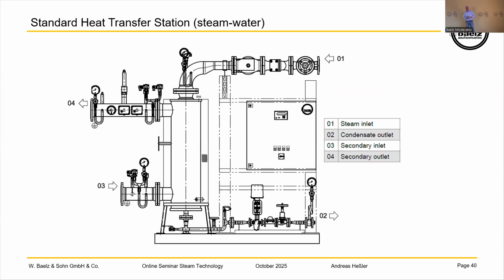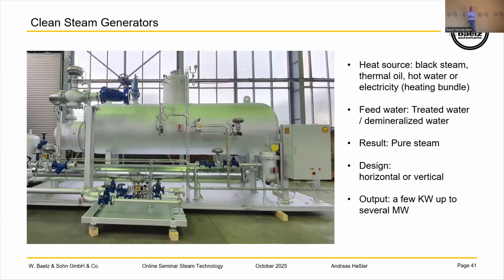Here is just a picture of how a complete or compact unit looks. You see the inlet and the outlet connections, just for your information. The next one would be clean steam generators, where we put black steam, thermal oil, hot water or electricity. The feed water is normally demineralized water or clear water, and we produce pure steam for that. This design can be horizontal or vertical, and the output is like the other ones, from a few kilowatts up to several megawatts, which we can all handle.